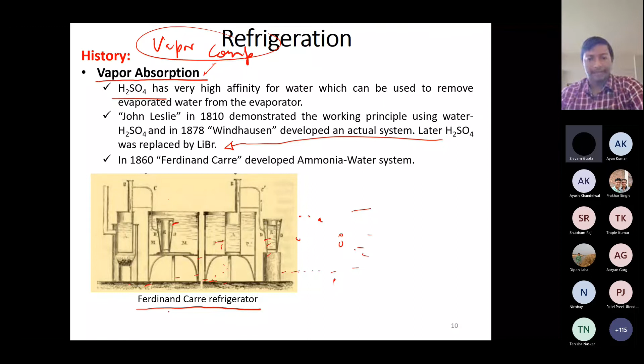Nowadays these systems are actually available. Typically their size is of the order of a few hundred kilowatts, which is the amount of refrigeration they produce. Compare that to your refrigerator at home, which produces about 150 to 200 watts maximum, unless it is an Almirah-sized refrigerator, which might produce 500 to 600 watts. An air conditioning unit produces 5 kilowatts if you have a 1.5 ton AC. These systems normally start at 100 kilowatts if you want to buy them, and they require a huge amount of heat, probably 150 to 200 kilowatts of heat.